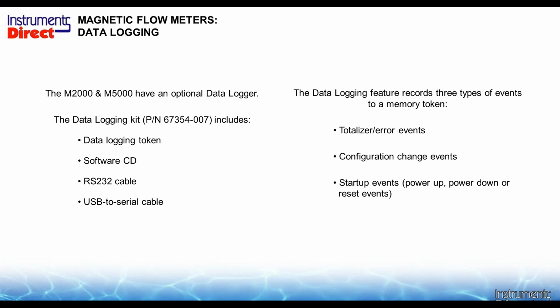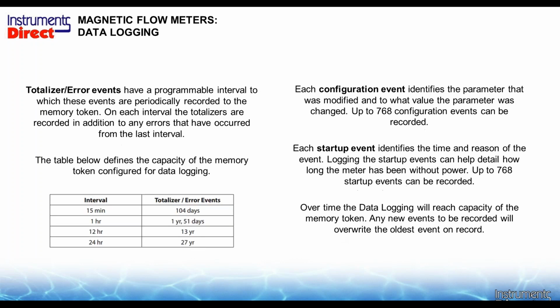And the onboard logger is very basic. It's designed primarily for totalizer monitoring and error events. So if you want to look at your daily totals, weekly totals, monthly totals, that's when you're basically going to take a look and use the data logging function there. To do that, you're going to need a data logging kit, and this data logging kit includes a logging token, the software, an RS-232 cable, and then, since no one else has serial ports on their computers anymore, you need to interface that from RS-232 to USB so you can use the information there. So it's a very basic logger there, mostly used for totalization of daily totals and things like that.